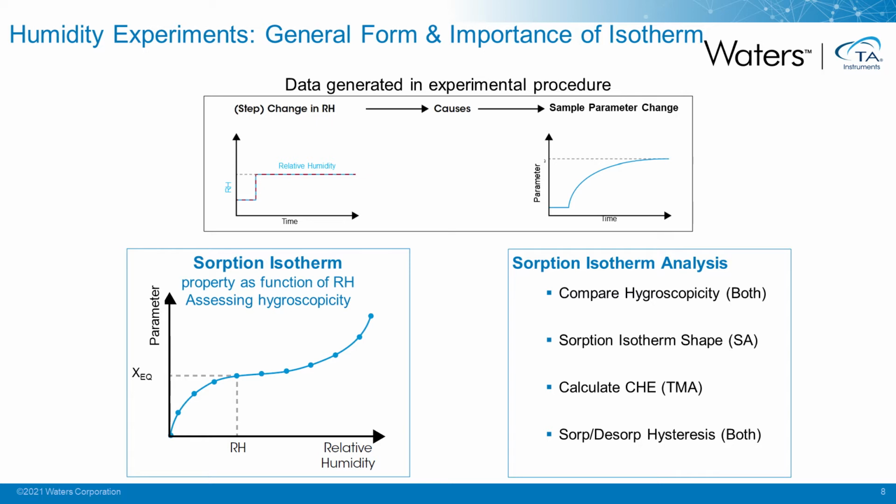And then you can look at both sorption and desorption curves to understand whether there's hysteresis in the curve. Does the sample release water as easily as it takes up water? Again, this is something that's important to see in both instruments.